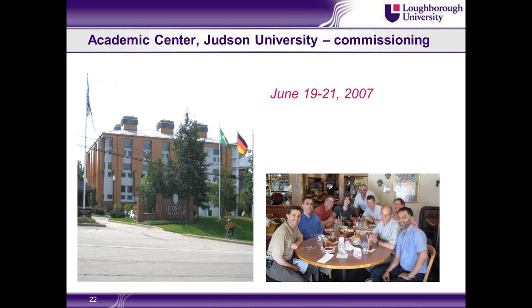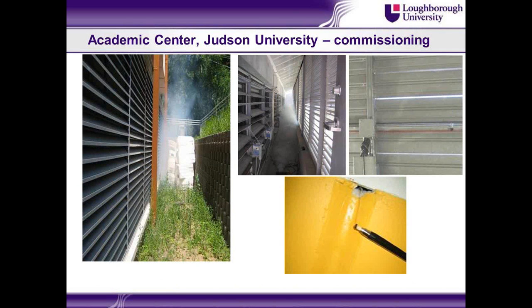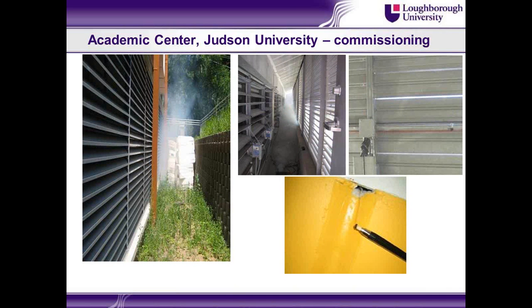Walked around the building, pleased with how it looked, went to have a look at the inlet dampers, stood around by the inlet dampers, and felt a lovely cool breeze. That's pleasant. Until we realised the cool breeze was leaking out of the building. So we were standing by the dampers, and this cool breeze, obviously in mechanical cooling mode, height of summer, so the plenum was being pressurised with cooled air, and that mechanically cooled air was leaking out into Illinois. Oops, we have to go back. Yeah. So we asked them to close the dampers, and that's what the closed dampers looked like.